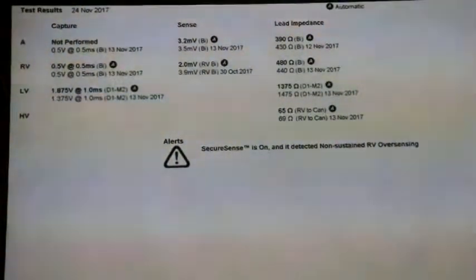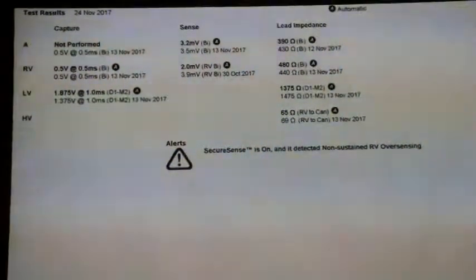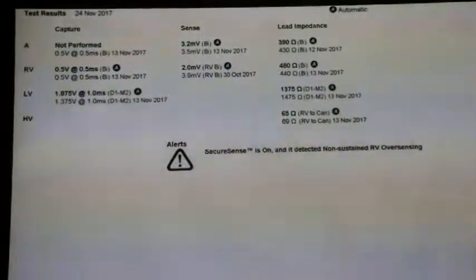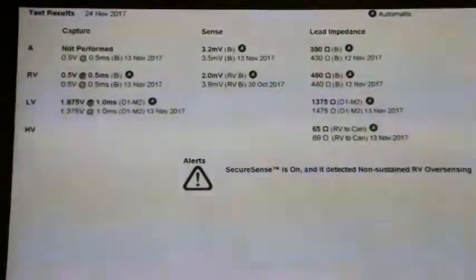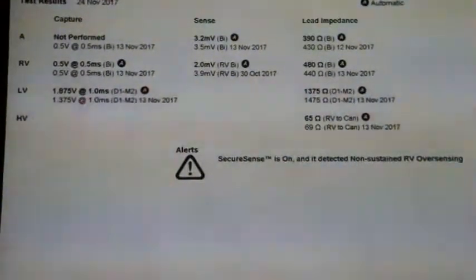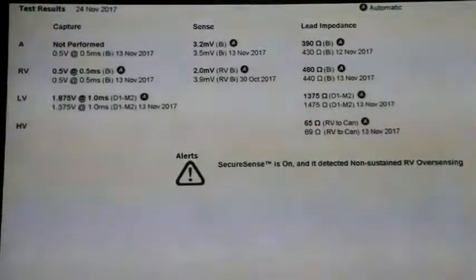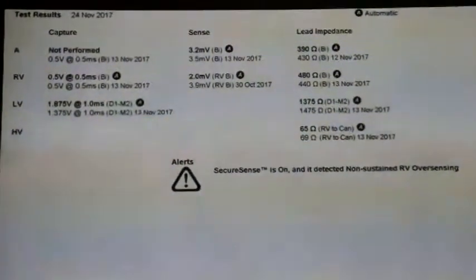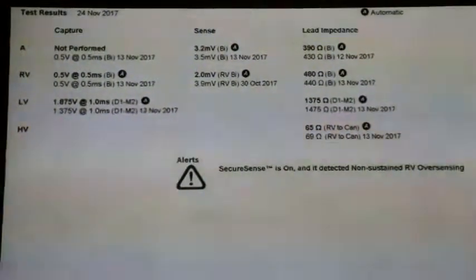You need to look at trends. This one measurement here means nothing to me. If someone sends me a troubleshooting case and that's one number, I'm like, I don't know what that means. I want to look at the long-term trend. And this was long-term trending high. Well, it's okay. It's no problem. The lead's working fine. It's got a good threshold. With high impedance, we're going to hardly suck any current out of this battery for the LV lead. This is exactly what we want.